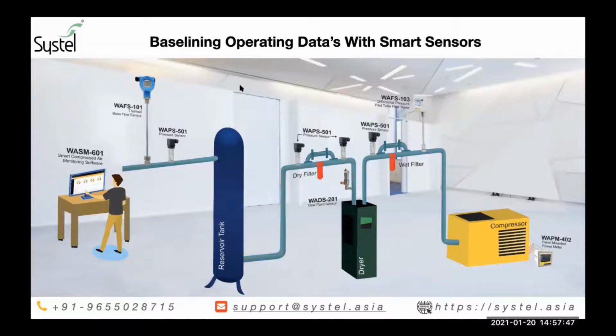And then this data is remotely sent to our smart compressed air management software. The software has an artificial intelligence program in it. Based on the specific power inputs that the software receives from the compressors, it can also give you an indication of the most efficient compressor combination to run for achieving lower energy consumption.